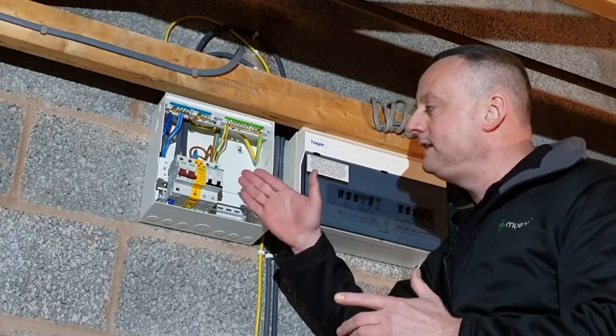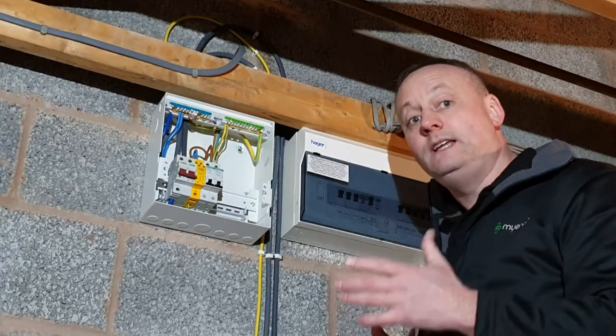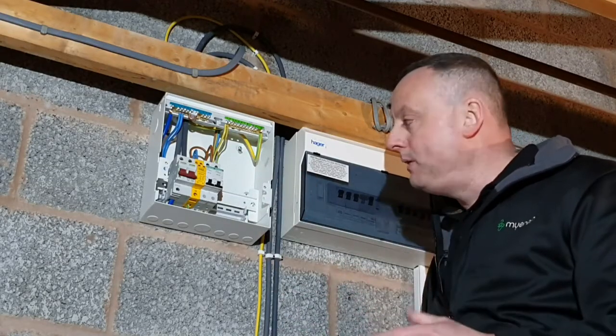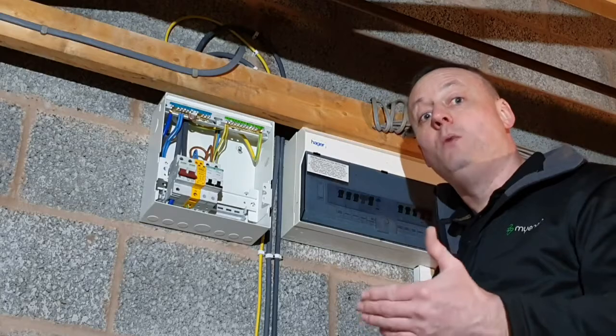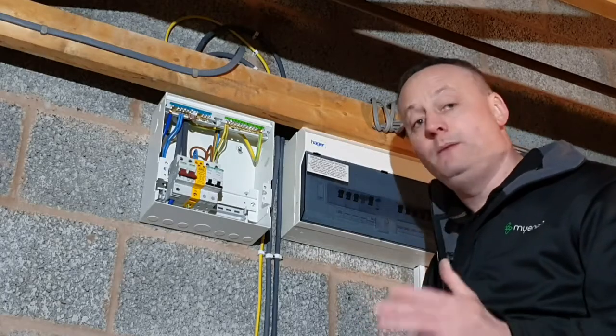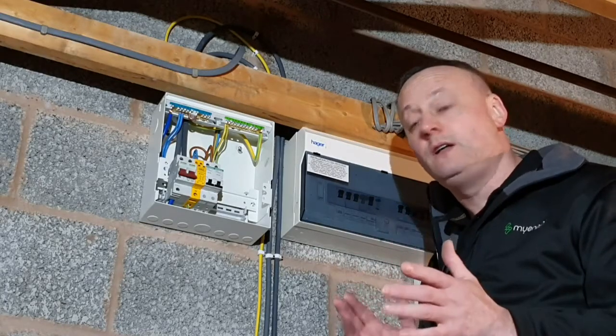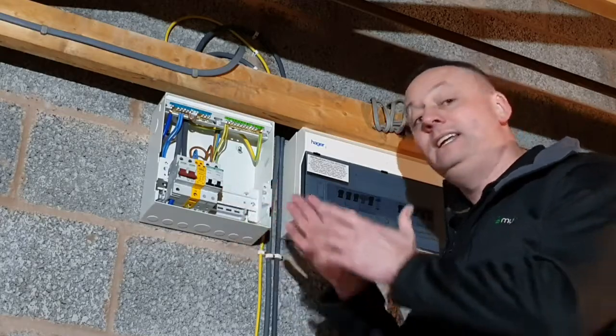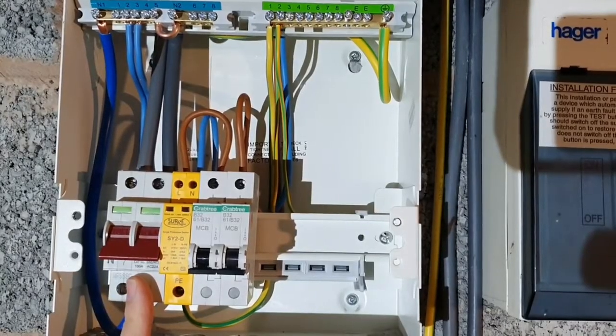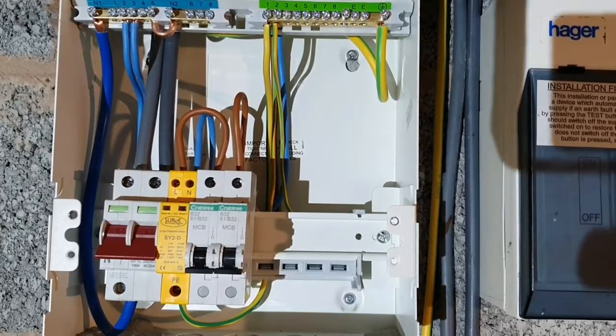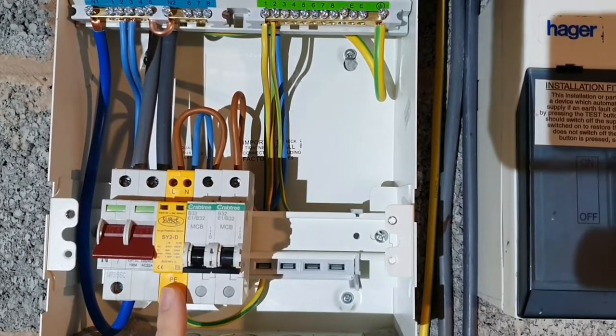Also, you would need to consider this to be an A-type RCD as a minimum. We know the technology built within the Zappi unit will mean that no more than 6 milliamps of DC will appear in the line and neutral conductor, and therefore an A-type RCD at this end would also be handled that 6 milliamps current. Okay then, Gary, so just one more thing worth mentioning at this stage.